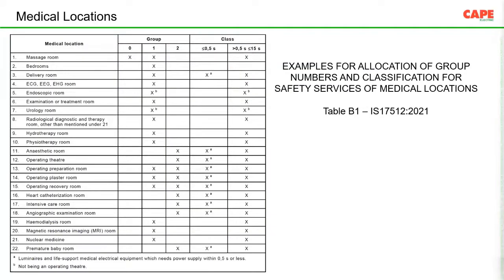But when it comes to the electrical installation, what is required is, I'm showing you Table B1 of IS 17512/2021, examples for allocation of group numbers and classification for safety services in medical location. Here on the left side, you can see some typical examples. For example, massage rooms, delivery rooms, how to categorize. Say, for example, anesthetic room is a group 2 location, operation theater is a group 2 location, then heart catheterization room is a group 2 location.